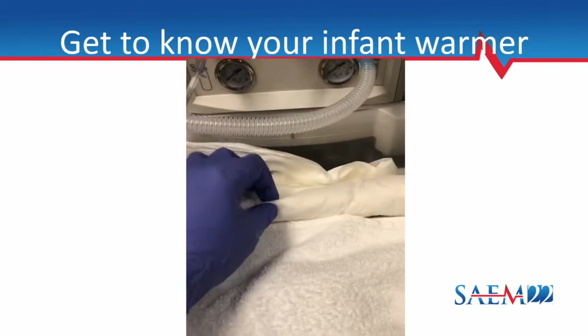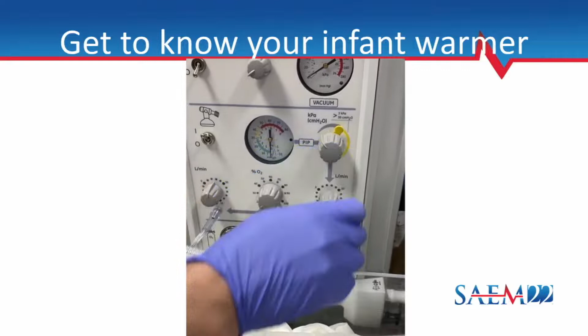In addition to that, you can use your infant warmer as a pressure-controlled ventilator. So the first thing you're going to do is connect your T-piece resuscitator, set your FiO2 to room air, 21%. You're going to want to set your flow rate to 10 liters per minute using this knob here. And then finally, you'll set your peak inspiratory pressure using this knob here, or your PIP. We'll talk to you about how to adjust that.